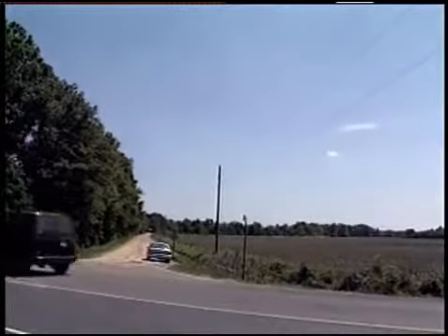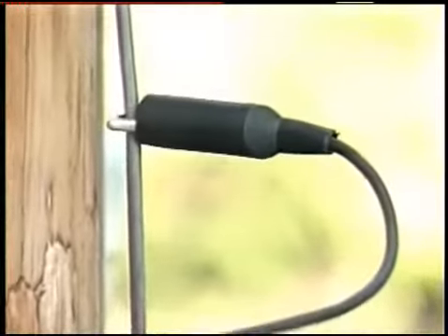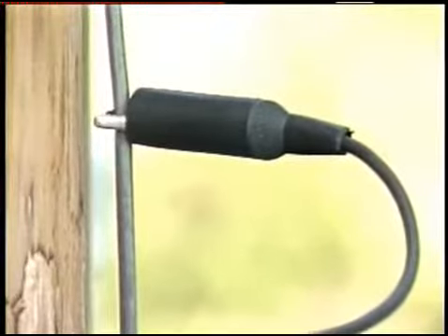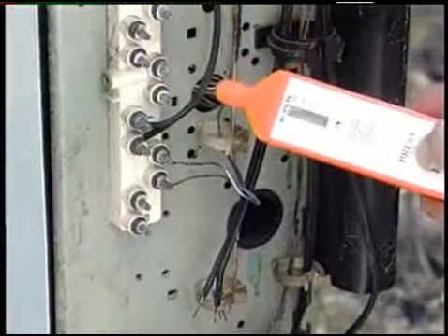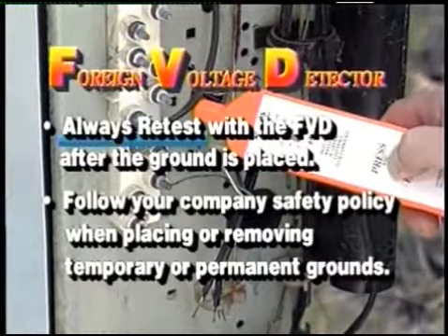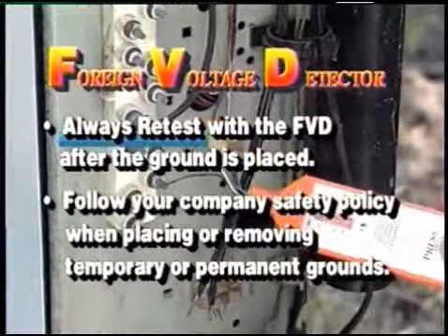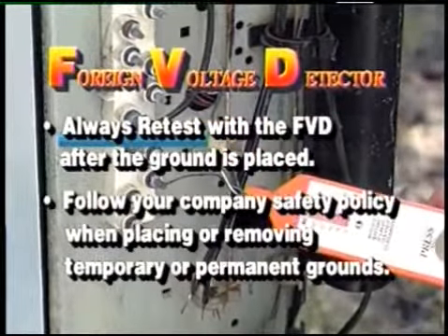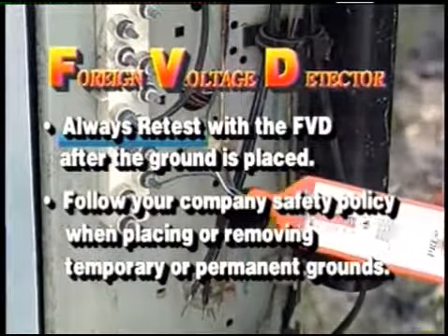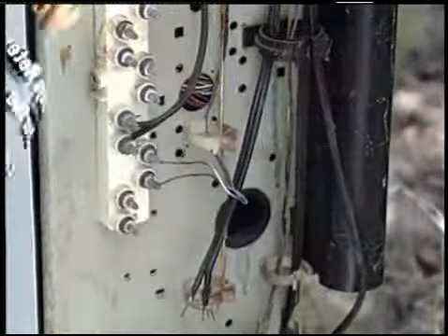It is recommended that a visual inspection of the route be made to determine that no physical hazards exist. After this has been determined, to make the situation safe, simply connect the floating C-wire to a temporary ground. Always retest with the F.V.D. after the ground is placed. And remember to follow your company's safety policy when placing or removing temporary or permanent grounds.